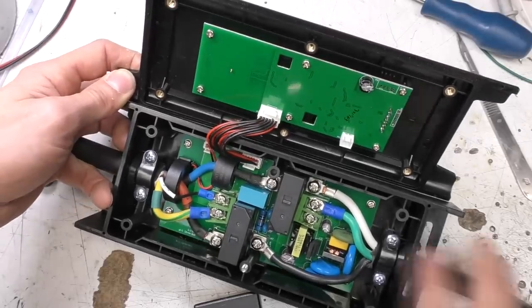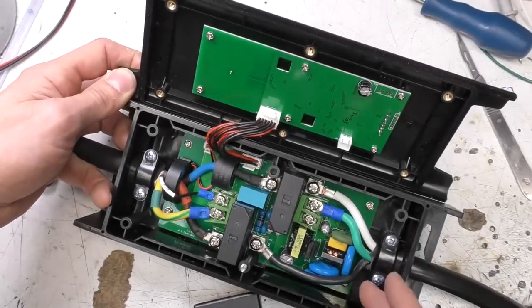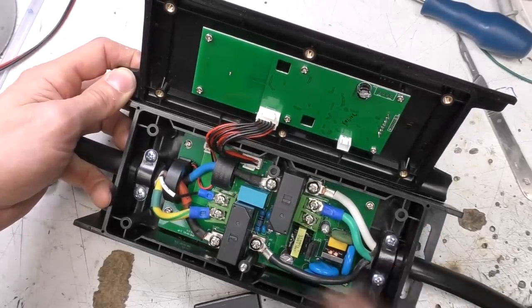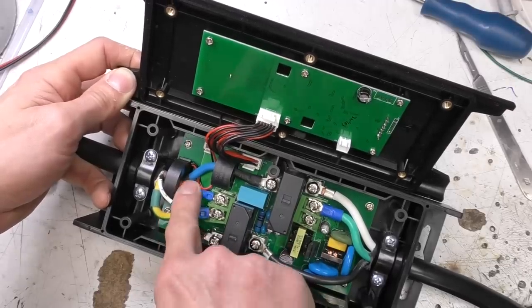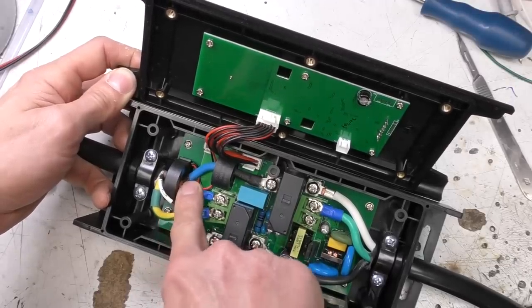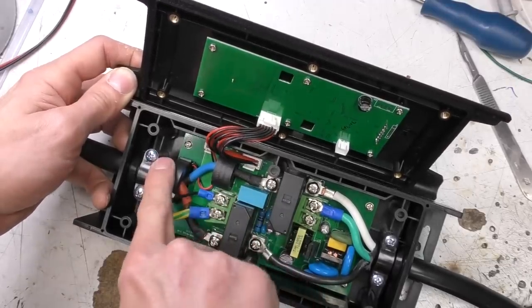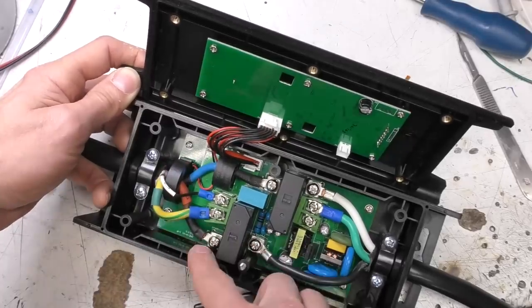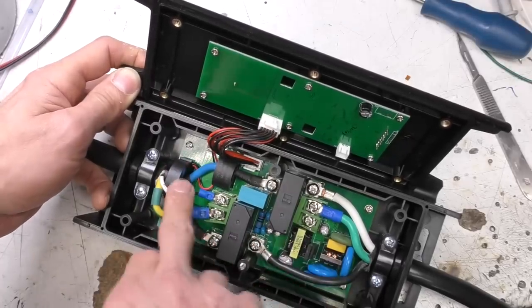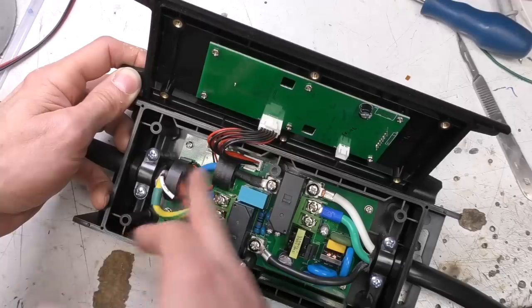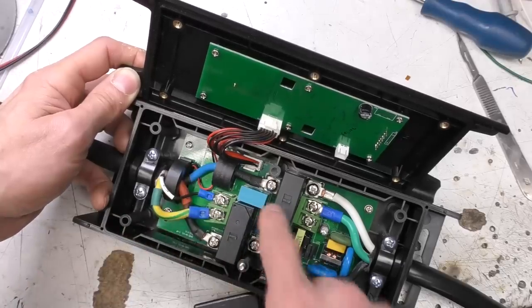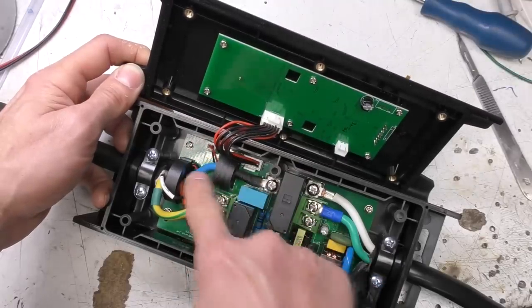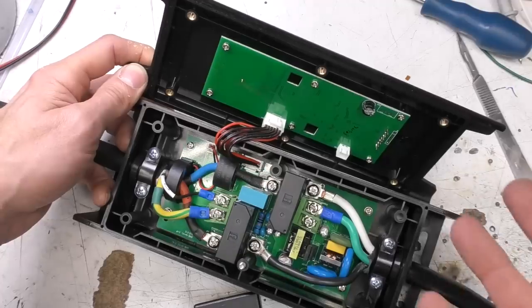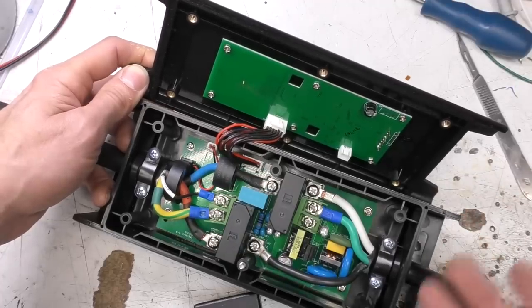The overall layout is a bit less cramped, but also it's a lot easier to get apart, because here they've put the earth leakage current transformer over the cables. Instead of being attached to the PCB, it's actually a separate device that plugs in, so although you may or may not be able to get those tags back through the transformer, it doesn't matter because the whole thing can come away, so you can get the board out. And this single one for the current measure transformer is small enough that it will actually pass through the transformer, so you can get all these boards out really easily, whereas it's an absolute pain on the other one.